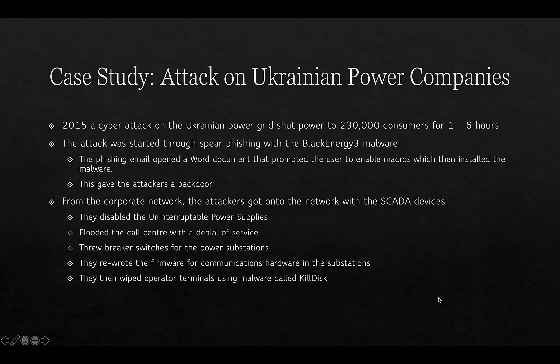In 2015, a cyber attack on the Ukrainian power grid shut power to 230,000 consumers for one to six hours. The attack started through spear phishing with malware called Black Energy 3 attached to emails. The phishing email opened a Word document prompting the user to enable macros, installing the malware and giving attackers a backdoor. From the corporate network, attackers got onto the SCADA network, disabled the uninterruptible power supplies (UPS), flooded the call center with a denial of service, tripped breaker switches for power substations, and rewrote firmware for communications hardware in the substations, making remediation difficult.